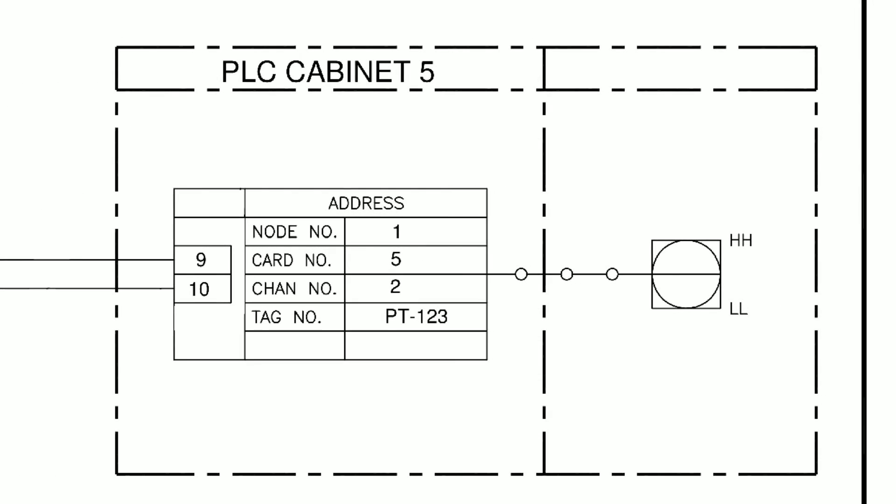Moving on to PLC Cabinet 5 we can see the final connection point. We can see that this is connected to node 1, CARD 5, channel 2. Now this information is more to do with the PLC infrastructure and allows us to locate the actual individual card where our signal from our pressure transmitter is connected into.